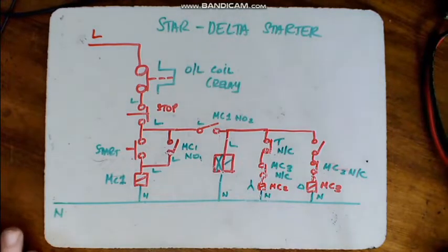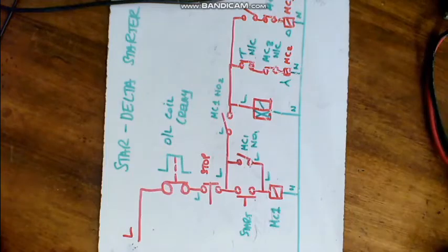Right, at this point make sure you have the diagram drawn, because I'm going to now draw the same diagram as a ladder diagram. I don't have enough space to write both and show this one at the same time, so please, if you can, draw this one quickly, and then you can follow as we go and convert this diagram to a ladder diagram. The best thing to do is to flip this sideways. Now you have your live and your neutral. So all you have to do is draw these same things going across between the live and the neutral, and that will be your ladder diagram.